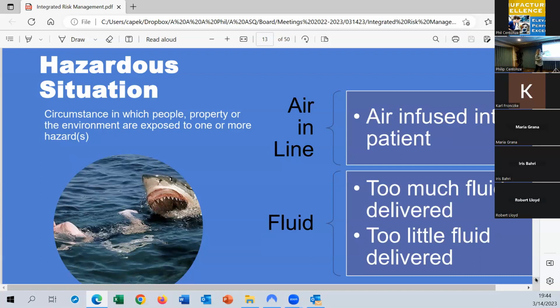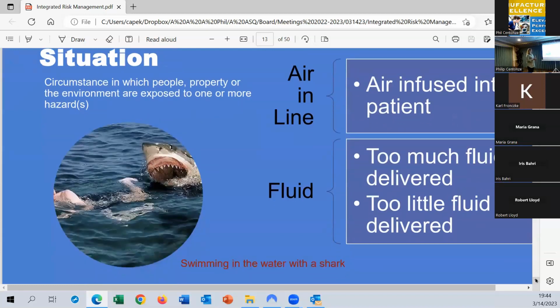With different hazards, if I had a hazard like air in the line, for an infusion pump, the hazardous situation is that I infuse that air into the patient. That air might cause harm, or it might not. There's a probability that it could cause an air embolism, for example, or maybe just pain. With an infusion pump, fluid could be a hazard, and delivering too much or too little would be the hazardous situation, right? The patient gets either an overdose or an underdose.